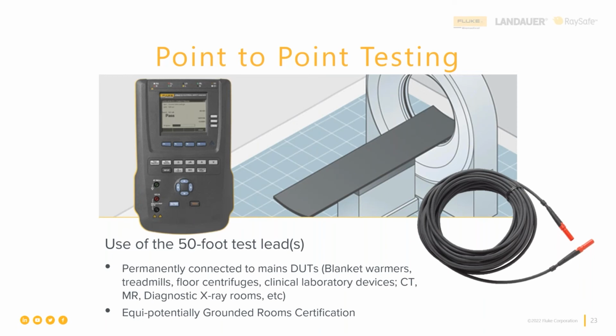And we provide 50-foot test leads, specifically so that you can connect your ground to either that equipotential grounding point in the room or to a reference point, because we can't break into a permanent mains connection to get at ground. At a reference point that we choose, the measurements we make with our measurement lead are leakage current with respect to that reference point, which is not necessarily ground.